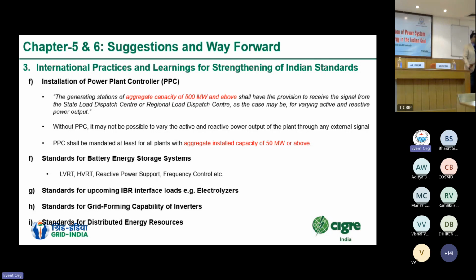Standards need to be evolved for the grid forming capability of inverters. The inverters we have in our Indian power system are mostly grid following type. With grid following inverters, it becomes difficult to ensure system stability when grids become weak, penetration becomes higher, and conventional generators retire. So a certain chunk of generation out of the RE plants expected to come in future needs to be of grid forming type. Grid forming inverters have proved to be beneficial under a high RE penetration regime, so these can be thought of. Then, with the expected high distributed energy resources in the future grid, detailed standards on similar lines may certainly be evolved.